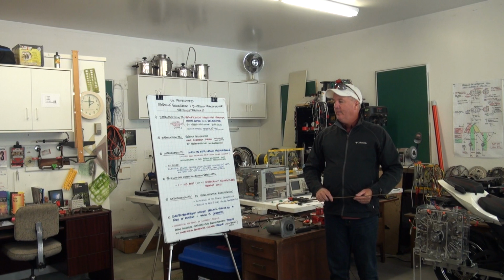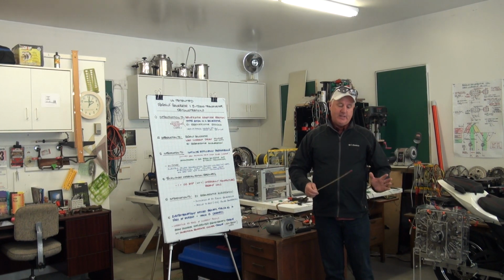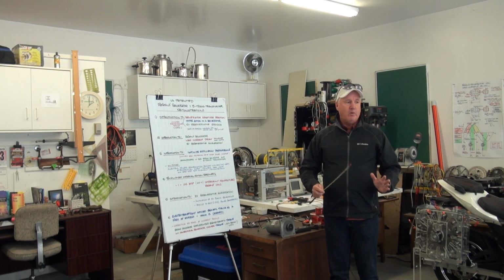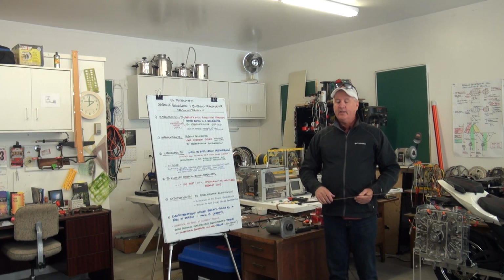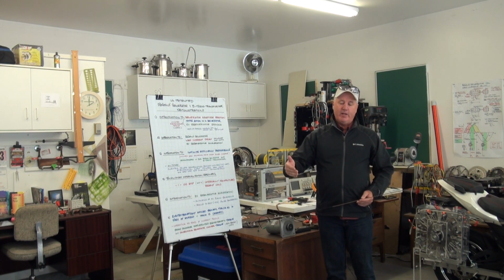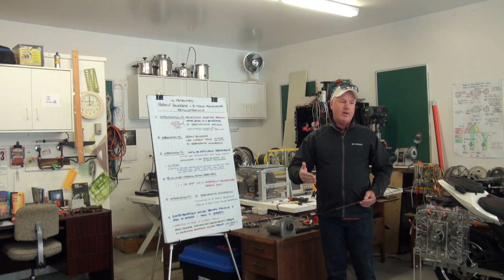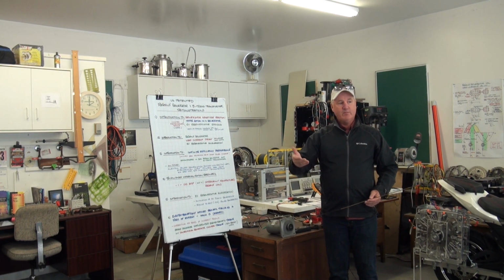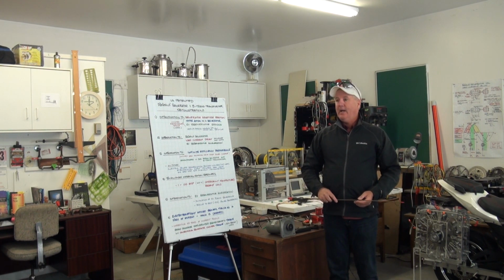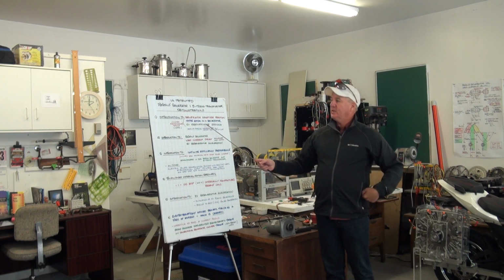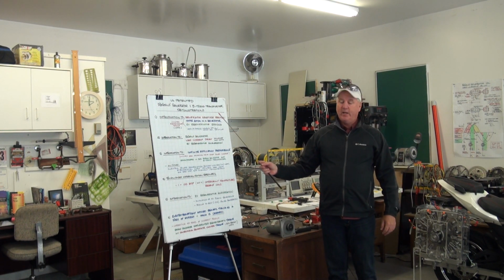Basically what that means is if you have a 1 megawatt generator that's delivering a megawatt to the grid, you need a minimum of 1 megawatt, or 1 million watts, of mechanical input power driving that generator, because of generator armature reaction.